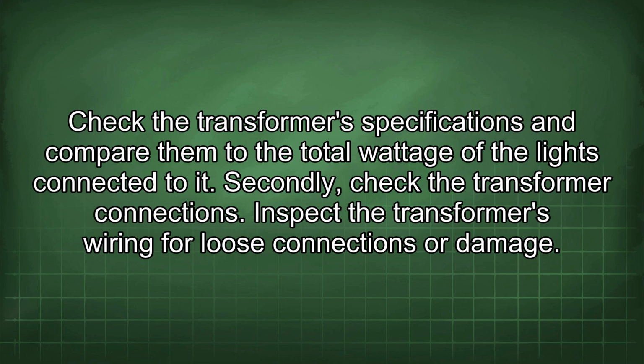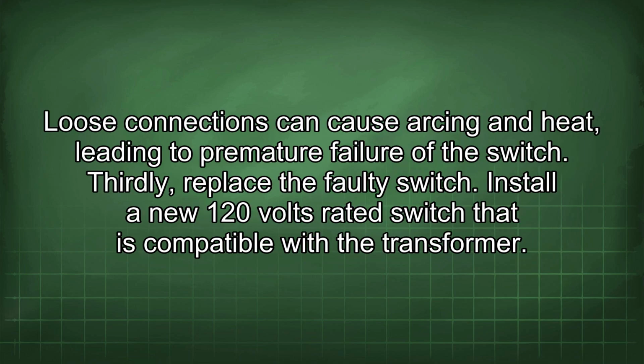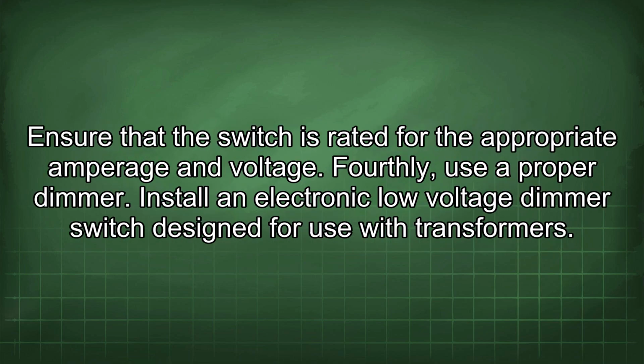Secondly, check the transformer connections. Inspect the transformer's wiring for loose connections or damage. Loose connections can cause arcing and heat, leading to premature failure of the switch. Thirdly, replace the faulty switch. Install a new 120 volts rated switch that is compatible with the transformer. Ensure that the switch is rated for the appropriate amperage and voltage.